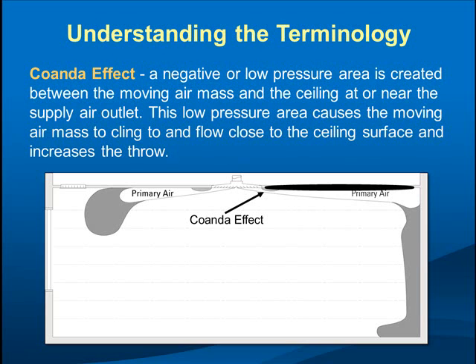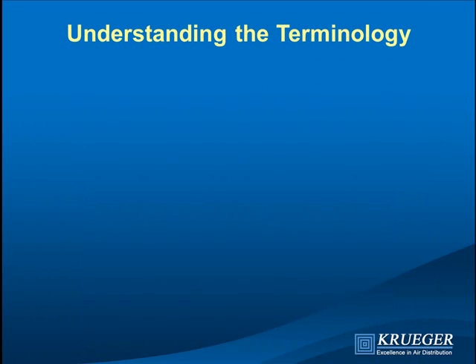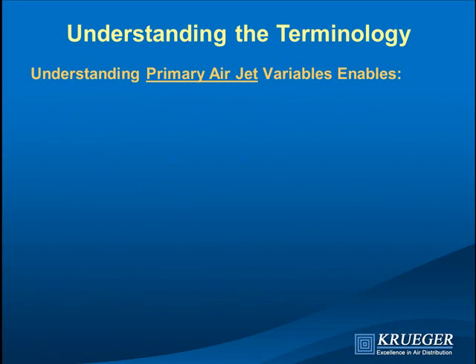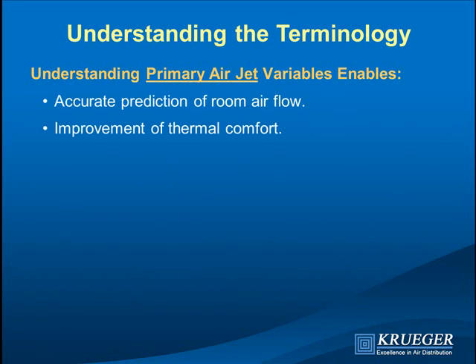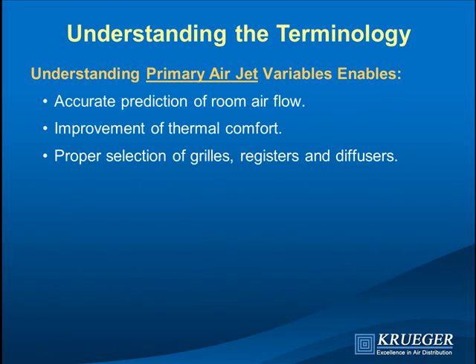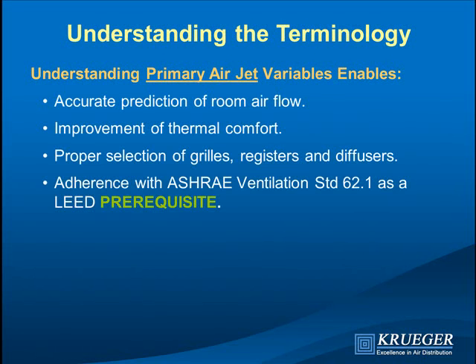Our goal is to get the jet to stick to the ceiling. We need to understand all these terms to accurately predict where the air will go, achieve thermal comfort — which is the goal — and make sure we select the right size of grill, register, or diffuser. We also have to comply with ASHRAE ventilation standard 62.1, which is a LEED prerequisite and is in a number of codes including the International Mechanical Code 2009.